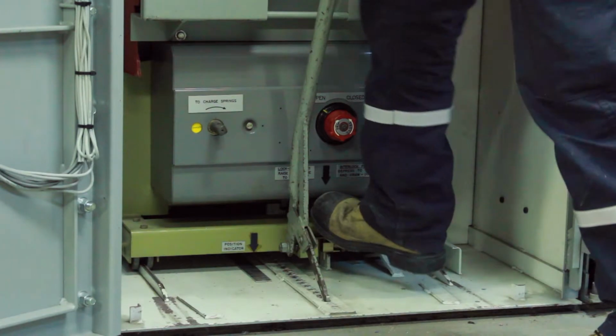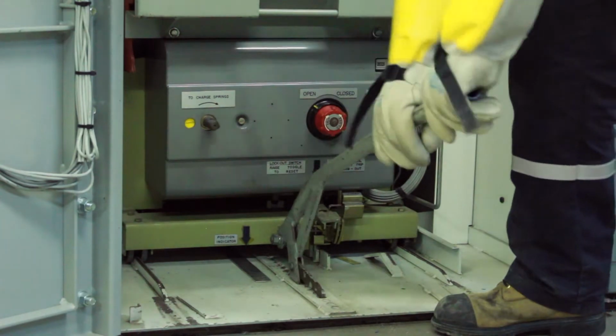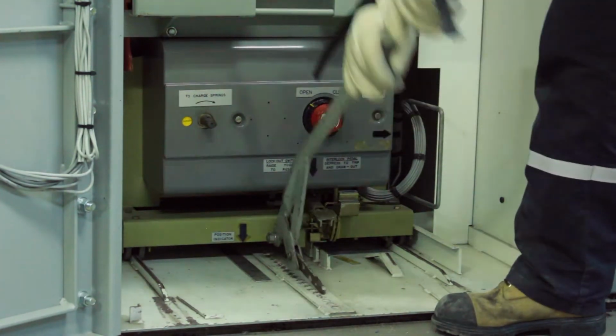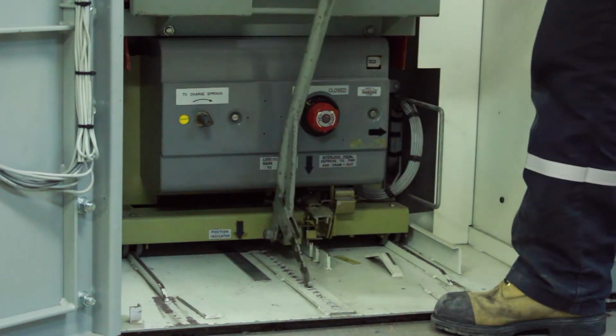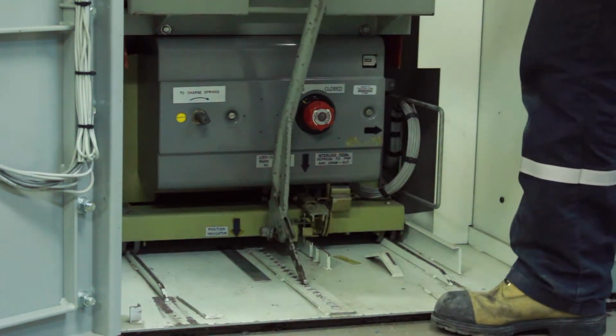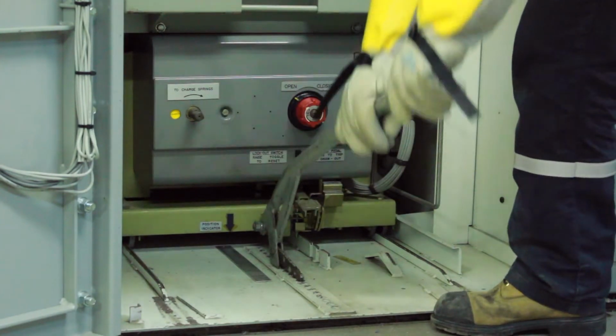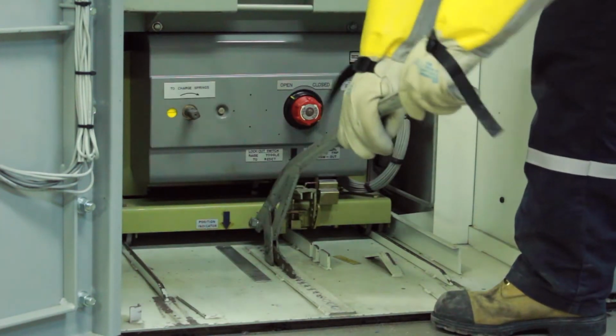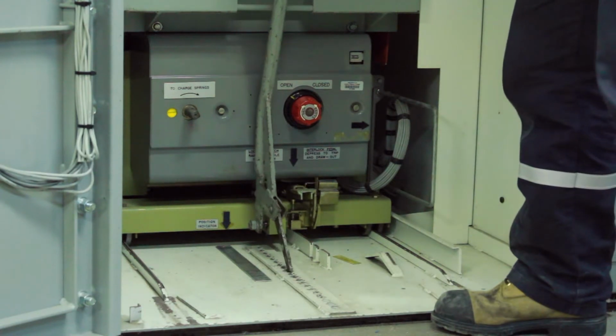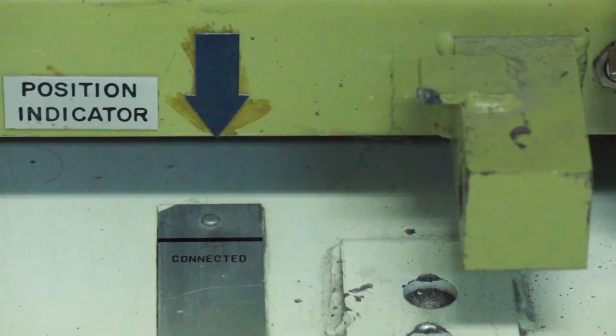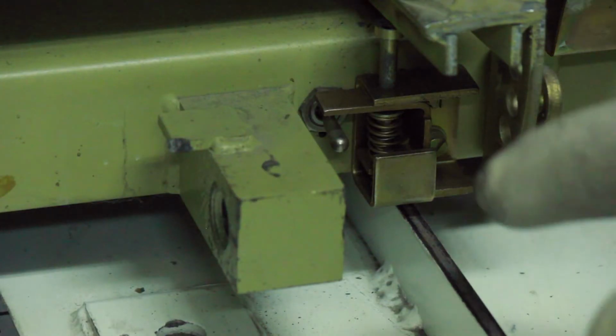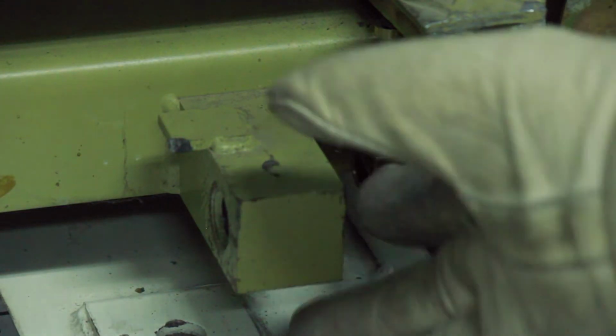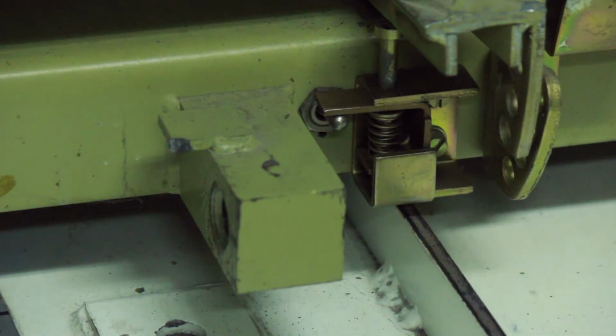Continue to rack the breaker onto the bus by pressing down on the interlock pedal and proceed to the connected position. As you rack the breaker from the test position to the bus, you'll hear an arcing, sizzling sound. Continue to rack the breaker without hesitation until it locks into the connected position. Verify that the position indicator is on the connected position, then remove the racking handle. Flip the toggle switch located under the interlock pedal upwards and close the breaker cell door.